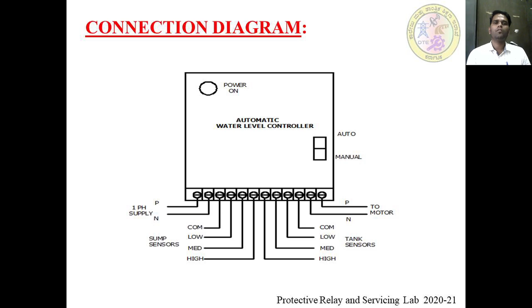One is the controller not switching on. The reason may be that there is no power supply coming to the controller, there might be a fuse blown in my controller, there might be no water in the sump, or it might be due to a faulty level sensor or faulty signal cables. Because of all these reasons, there may be a problem with the controller not switching on.